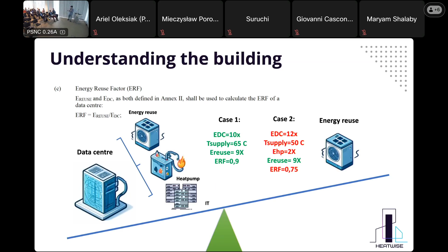So these are the things we are working on right now, trying to orchestrate the full system and make sure the return temperatures are controlled to answer the demand of the building, in terms of total accumulated energy and the return temperatures from the data center to the building. This way we make sure we achieve more efficient operation. Of course, there are also other things, like what happens if the heat pump is outside the building, so how we can justify and recalculate everything. Many people are now discussing this, but it's more realistic: if the temperatures are not good enough, then we have to increase them, right?